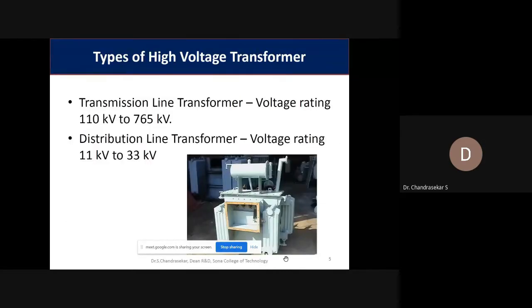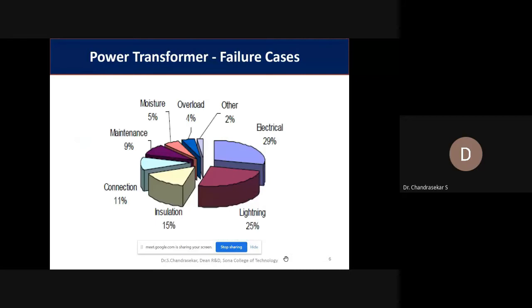This is a picture of a simple 11 kilovolt to 33 kilovolt distribution transformer. Even in transmission line transformers, as I already told, from 110 kilovolt to 765, and India has now even developed a 1200 kilovolt transformer, which I think was jointly developed by CPRI and BHEL and a couple of other big giants, an ultra high voltage transformer. Most of the causes of power transformer failure are natural, for example failure due to lightning. Lightning is 25%, which we cannot avoid because it's a natural phenomenon, and once lightning strikes, the entire thing bursts immediately.